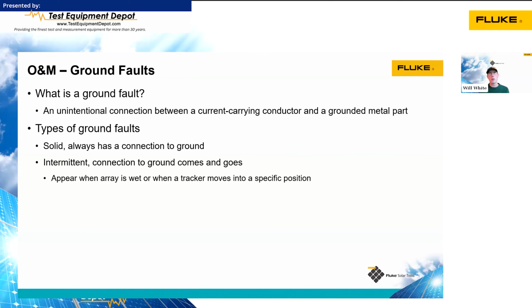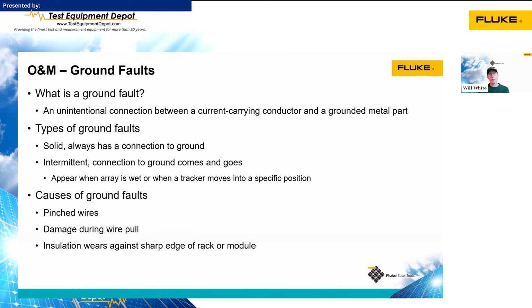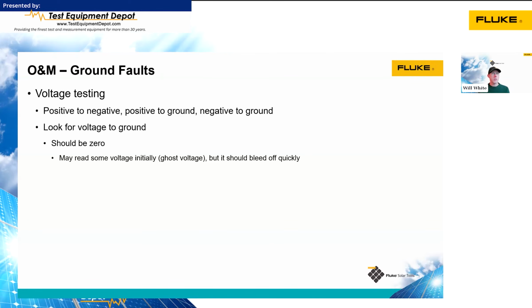There are several different things that could impact an intermittent ground fault. They're most common to show up in wet conditions, where there's reduced insulation value and increased connectivity between our conductor and our metal part. Sometimes you can see wires that are pinched by a tracker, so it moves into a certain position in the day, and then you get a ground fault when it hits that certain position. There are lots of causes of ground faults. Wires can be pinched between things like the module frame and the racking during installation, or damaged when they were installed. A very common one, which develops over time and starts as an intermittent ground fault and usually works its way into a solid ground fault, is when the insulation is rubbing, or the wire is rubbing up against some kind of part, and over time it rubs that insulation away, and now it's making contact to the metal there. Those are challenging to find.